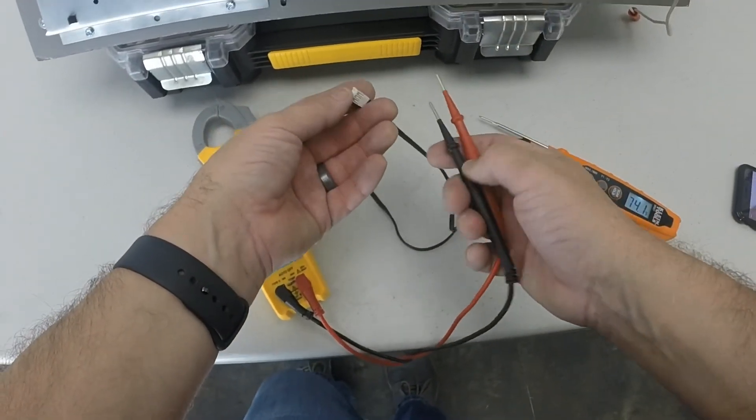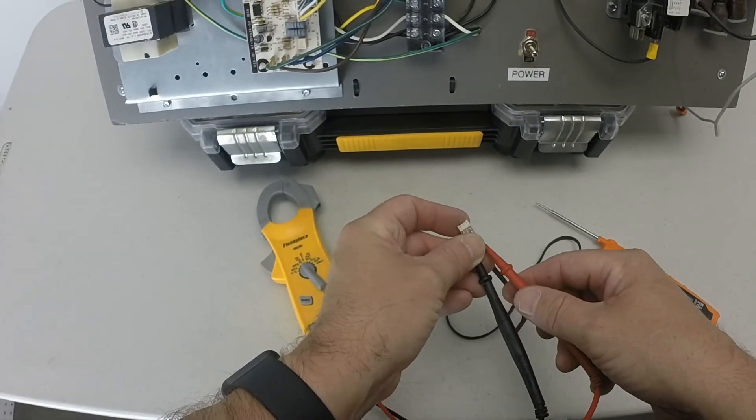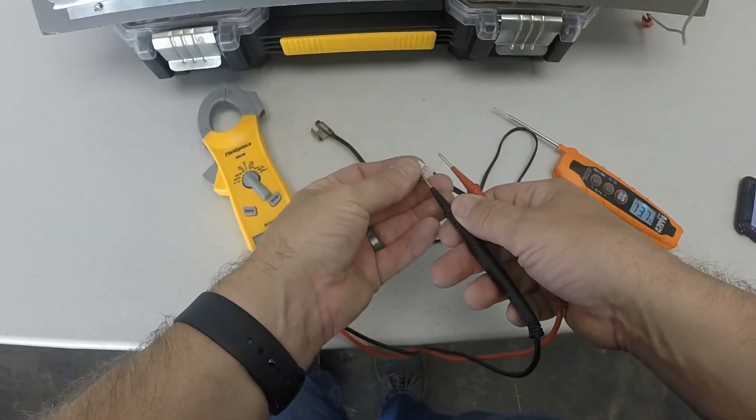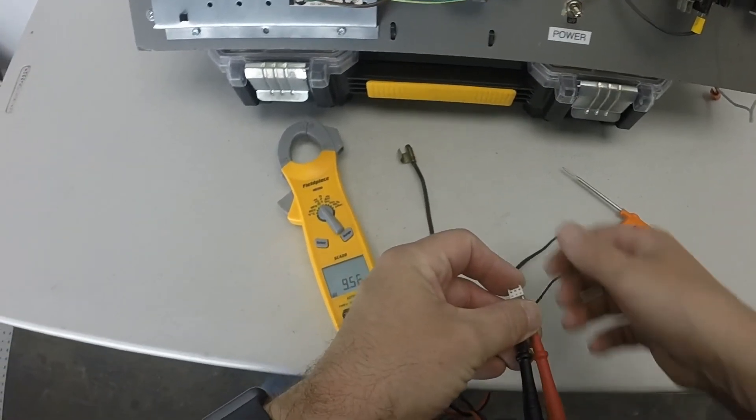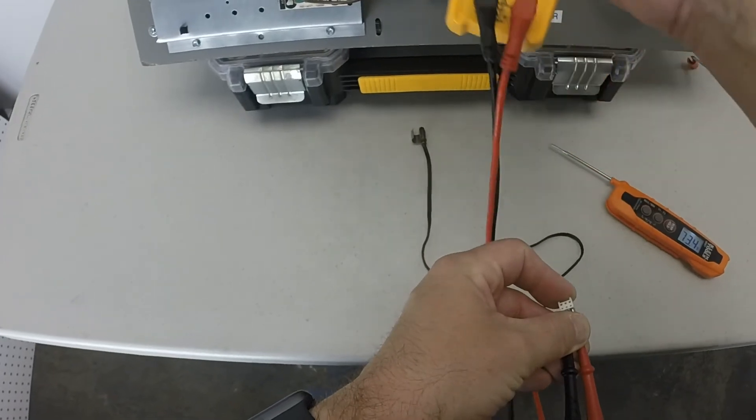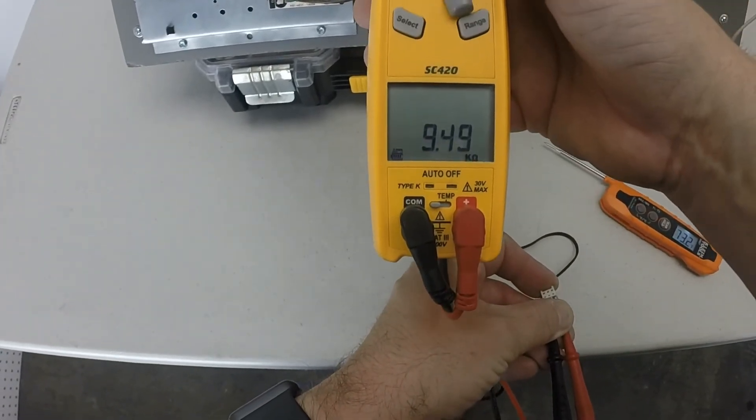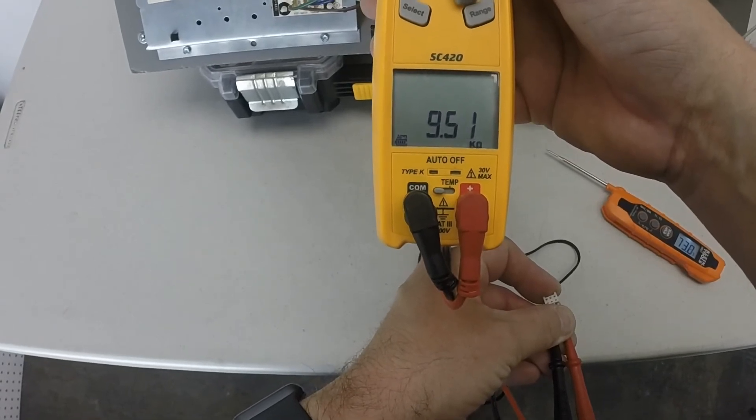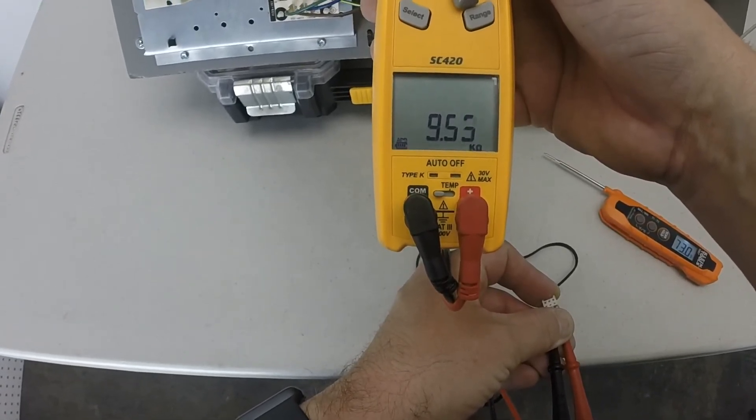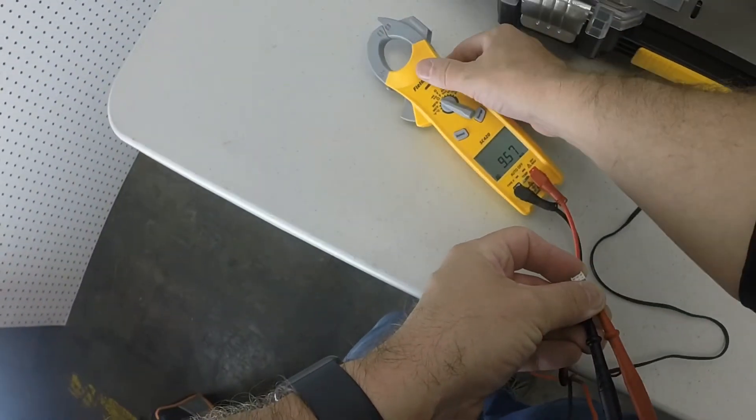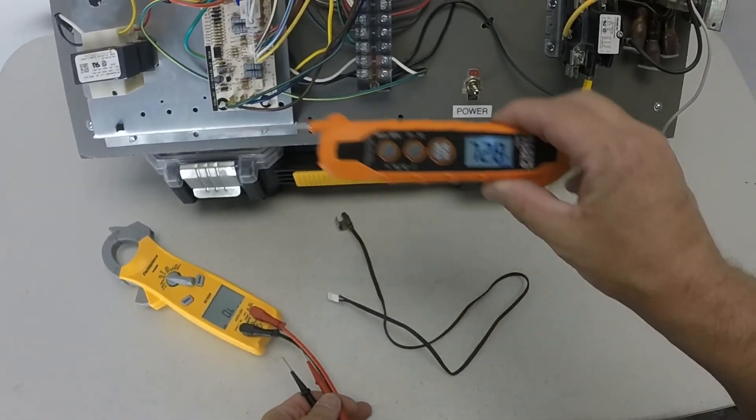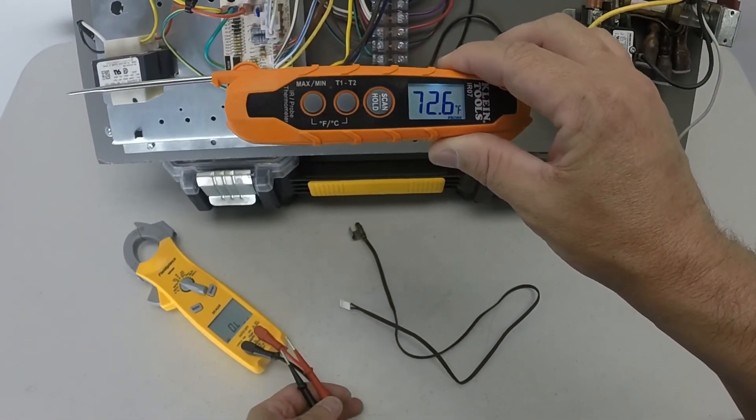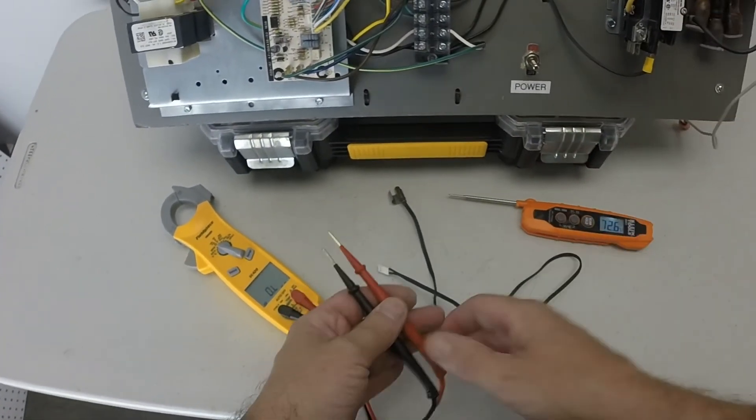This is the fun part, holding these two on there. This is where your helper comes in. All right, this one is a 9.4, 9.5. Give it a second. Let's go with 9.5. What are we checking that against? Well, we're checking that at 72 degrees. So we're going to have to go to our Ruud app and look at the chart.